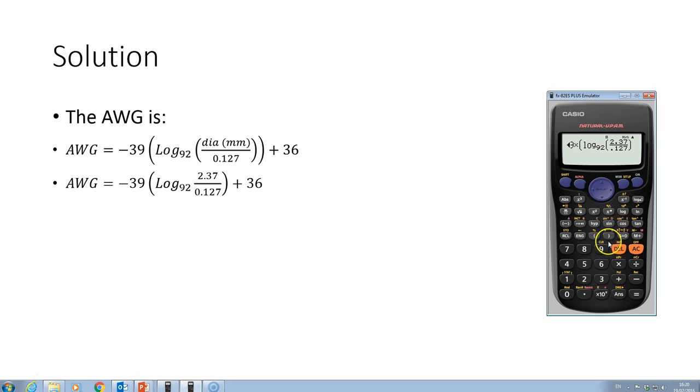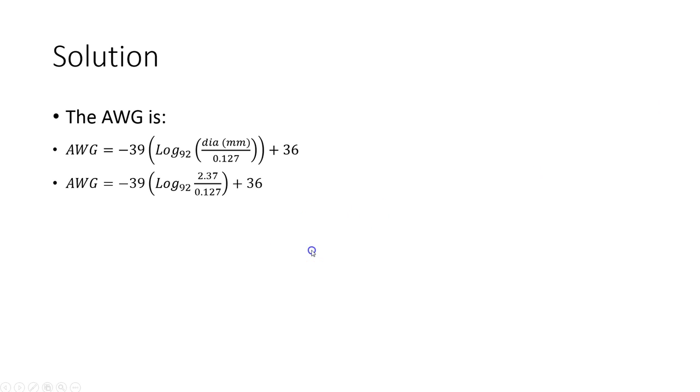And then I'm going to close off that bracket. And then we're going to add the 36. And that gives me a 10.75, which means when I actually specify the wire, I'll round down. And I'll use a gauge 10.